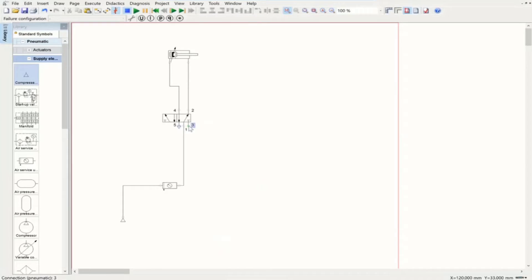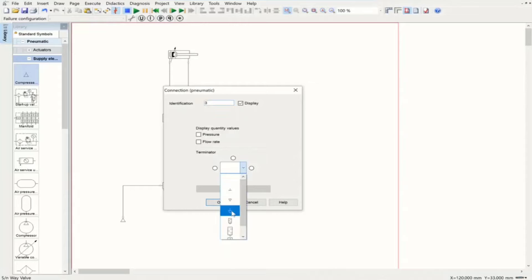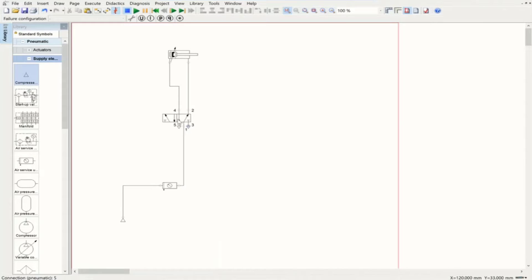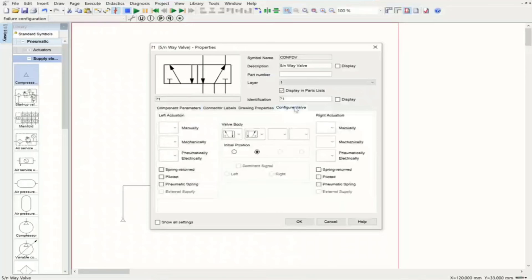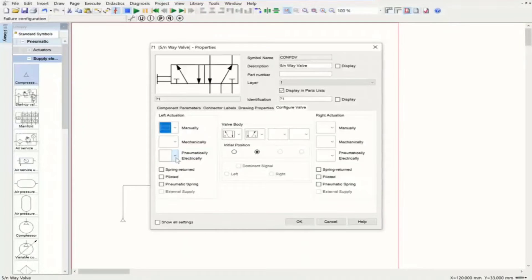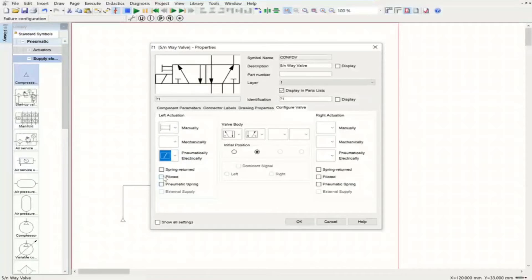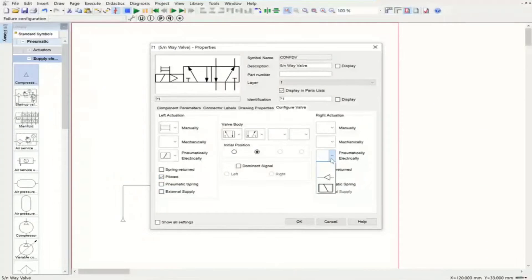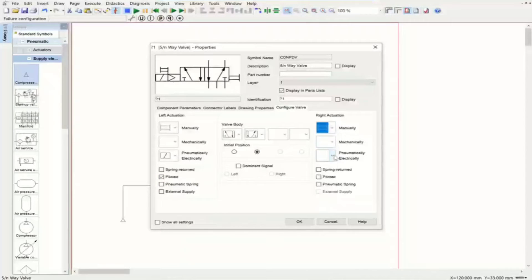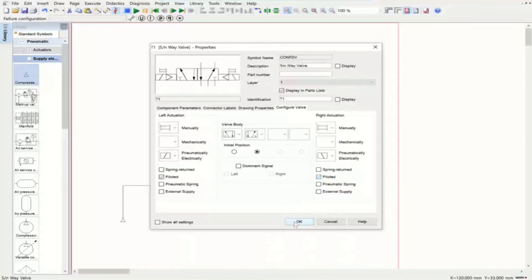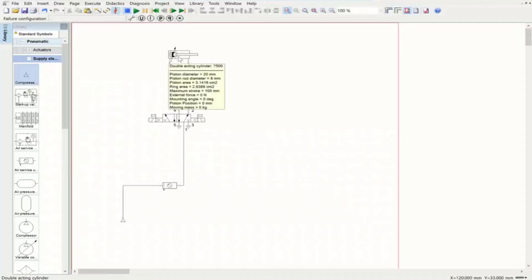We configure the valve — as you might remember, it was piloted with manual override and electrical actuation on both sides. So we set manual override and electrical actuation with pilot on one side, and the same on the other side. Then, as you might remember, we have two labels: the first one is S1, representing the fully retracted position, and the second one is S2, representing the fully advanced position.